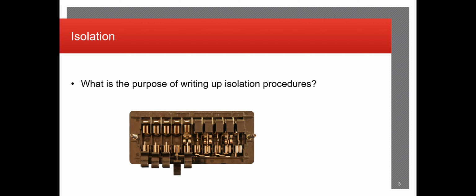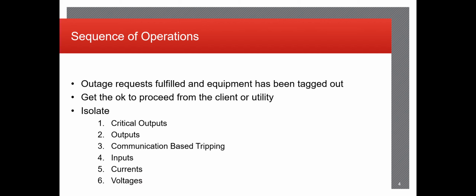This can be any form of DC or AC power that's being disrupted. So there's a standard sequence of operations for isolating a piece of equipment. In this case, we're going to be looking at a relay specifically to go along with the relay testing portion of this presentation. So the first step, as always, you want to get an outage request fulfilled and the equipment has been tagged out. This is usually done by communicating with the client in advance, coming up with a schedule, sticking to it, and then going through with it during the course of the isolation.